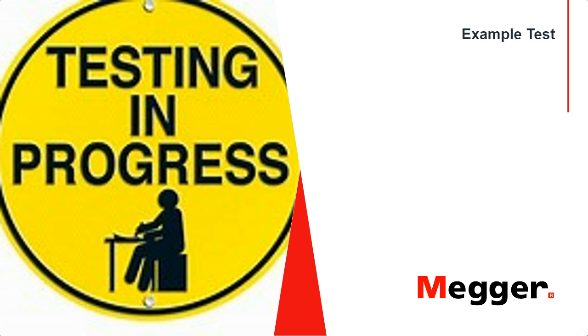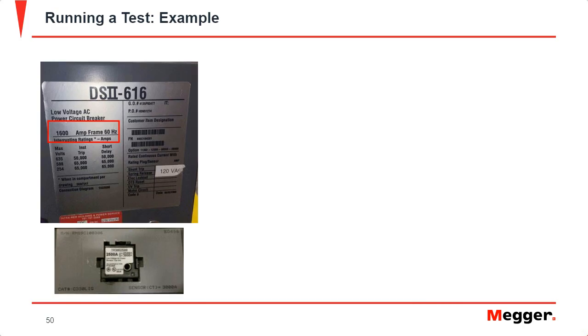Now we're going to go through an example test. For the people out there walking out for primary injection the first time, what should you do? What exactly is involved in a test? You walk out to the job site for the first time and you see, okay, here's the breaker itself. You take a look at the nameplate and you see it's a 1600 amp frame size breaker. This is actually a breaker that we tested when we went out and demoed a test set. So this is a real life experience. This 1600 amp breaker didn't have a sensor plug in it.